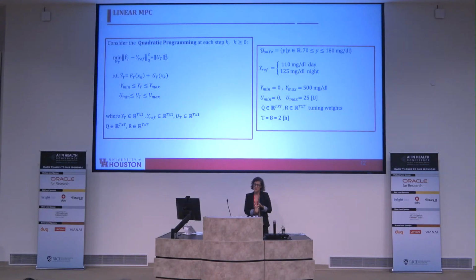The third part is that we can have a layered architecture by which we can shut off the pump, for instance, when we detect that the derivative, the glucose concentration is trending down, we can shut it off, and whatever is insulin on board will get cleared eventually. So yes, we have a variety of safety layers that we can implement other than the model. The model has to capture the true dynamics of the system to be efficient.